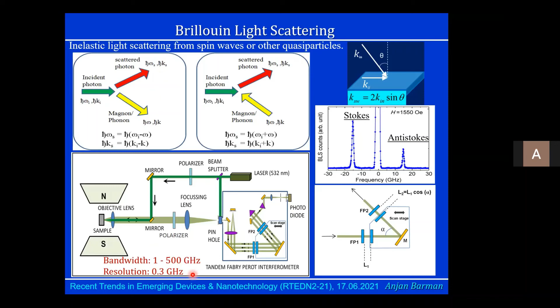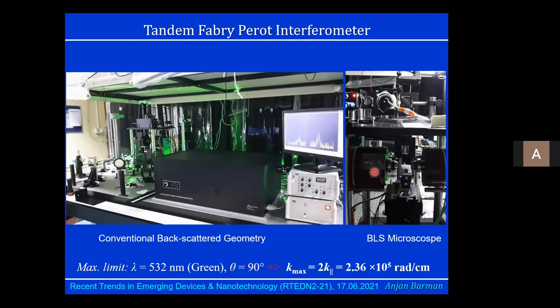Then after certain optics, it will be taken to this tandem Fabry-Perot interferometer, which has two Fabry-Perot interferometers at a certain angle, working together in tandem. And it is a multi-pass: there are 3 + 3, six-pass Fabry-Perot interferometers. By adjusting the angle and the difference, you can reject all the modes and keep only the mode you are trying to measure. The bandwidth is 1 to 500 gigahertz, and the resolution is about 0.3 gigahertz. This is Brillouin light scattering with a tandem Fabry-Perot interferometer in our lab, and this is a microfocus Brillouin light scattering microscope.